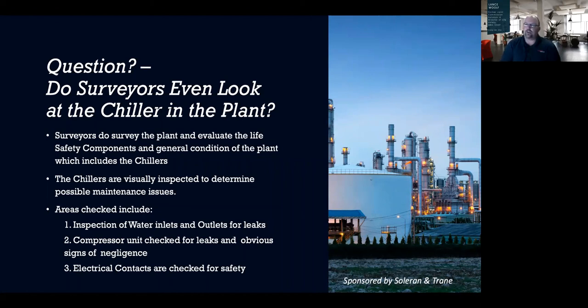And that comes back to the OSHA 1910 reference in regards to guard safety. And so there were a lot of findings just in that area, because obviously it took time to take that guard off to be able to get in the compressor to work on it. And so your vendor would come in and they worked around it so much that they felt the guard was more of a hindrance than a safety measure for them. So they took it off. So these are all things that, when you're looking at your chillers, take it back from a perspective of not specifically what you would do or how you work on it, but what a surveyor would look at. Change that hat a little bit when you're coming in and walking around your chiller unit.